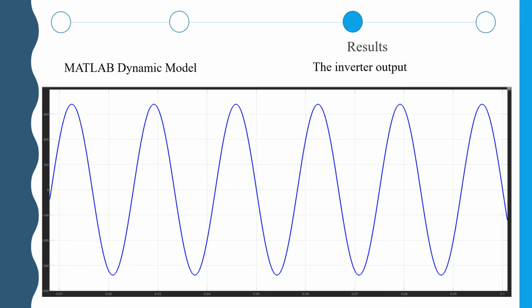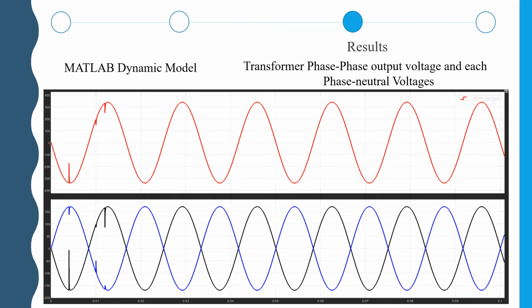The inverter output, as shown in this figure, is a pure sinusoidal wave, and also with frequency 60 Hz to meet the Canadian standard. As shown in the first graph, the phase-to-phase voltage is 340 volts peak, with approximately 240 volts RMS. And in the second graph, the phase-to-neutral voltage for each phase has approximately 120 volts RMS. All the waves have 60 Hz frequency and are free of harmonics, with a quick transient response while connecting the load part by part in the system startup.